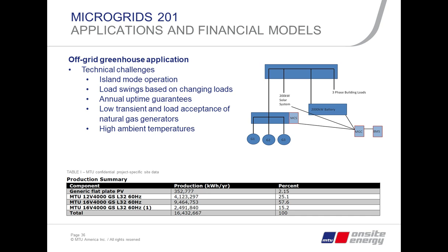Natural gas engines traditionally don't like transient loads being removed and added without some control. So the battery in this case offers grid forming and load leveling services, making sure we can transition the loads from generator 1 to generator 3 and back and forth as smoothly as possible to keep the engines running efficiently.